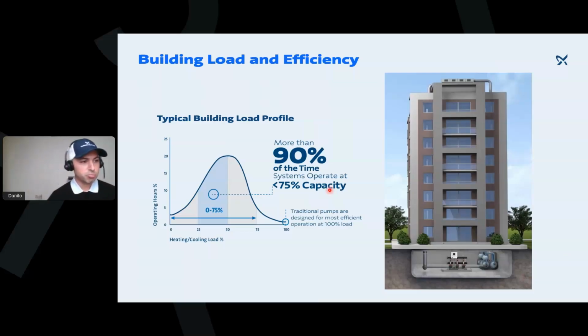Now let's talk about efficiency, as I mentioned, on part load conditions, right? What is the typical building load profile? So when we're looking at a building, at the bottom here, you can see in a percentage, right, of the load and the demand. Are the pumps running at 25%, 50%, 75, or 100% of the load? And then here you can also see the operating hours on the axis here.